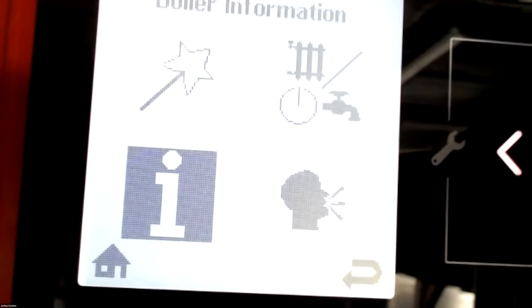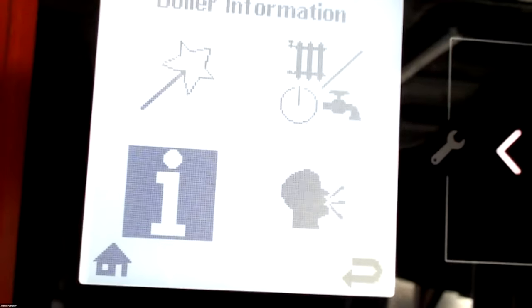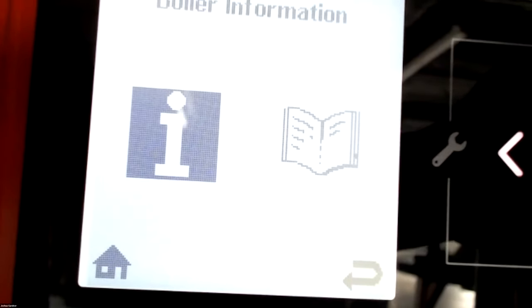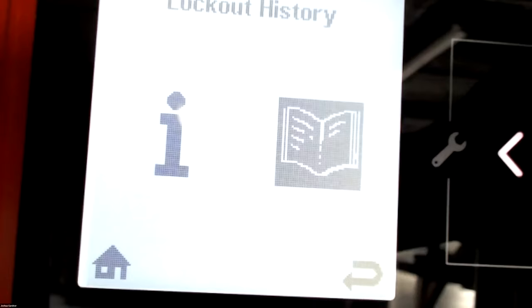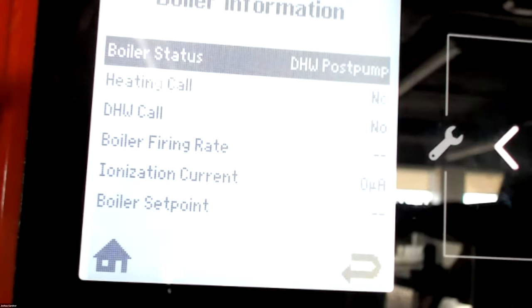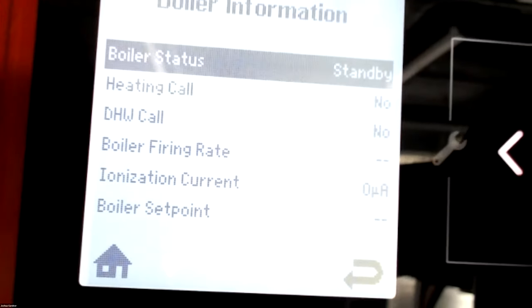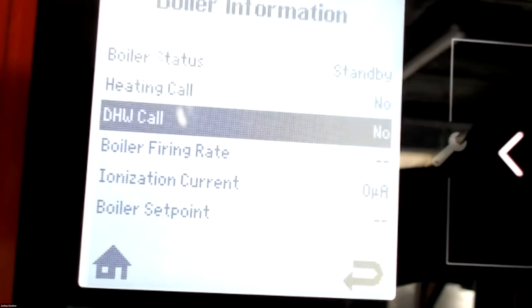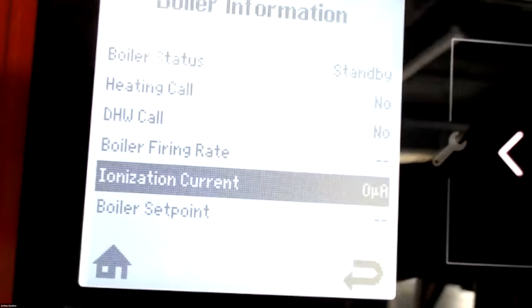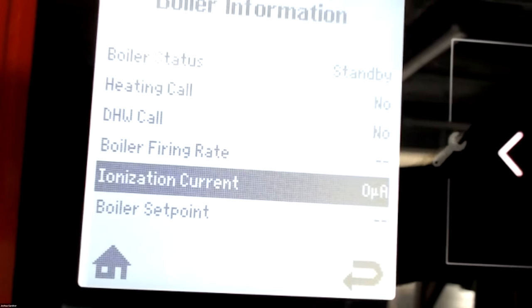Then going down here, your boiler information. This shows you your boiler info and shows your lockout history. So if we go to boiler info, it's going to tell us the status. So we're in standby now, the heating call, DHW call, firing rate, ionization current. You see that in live time while we're running.